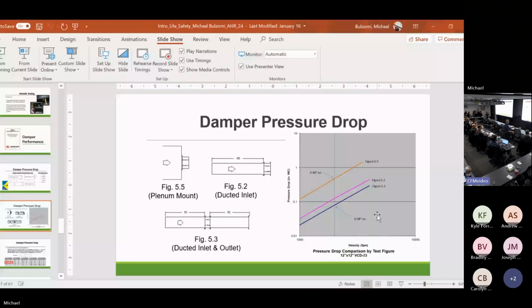So my 12 by 12 has a rated pressure drop of, let's say, 0.05 inches water column. My 13 by 13 could be a 0.2 of an inch pressure drop because I use blade stops. I use a different configuration. If you really want to be sure of the pressure drop, ask the manufacturer to provide you in the submittal with the as-built pressure drop of every single damper, and look at them and compare them. Now, all of you are going, I've never even considered that, right?